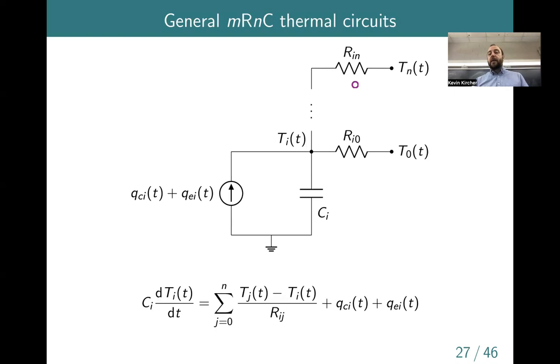Yes, thank you. So I just want to zoom out a little bit and say that when you start getting into these high order models and taking into account more sophisticated effects, it does get difficult to specify all these parameters. So in practice, what people will often do is they'll specify the form of the model using this sort of physical intuition, you know, what zones are connected to what other zones, things like that. But then you fit the parameters of the model using data that you observe from the building. So often that's an easier approach than a priori specifying all the numbers, the R's and the C's. Alex, I think you had a question.